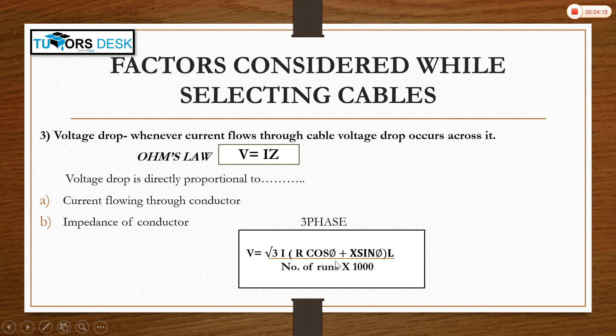Here are the formulas to calculate the voltage drop. For three phase, voltage drop is given by root 3 I (R cos phi + X sin phi) L divided by number of runs into 1000. For single phase supply, it is given by 2 I (R cos phi + X sin phi) L upon number of runs into 1000. And for DC voltage, it is given by 2 I R L upon number of runs into 1000.